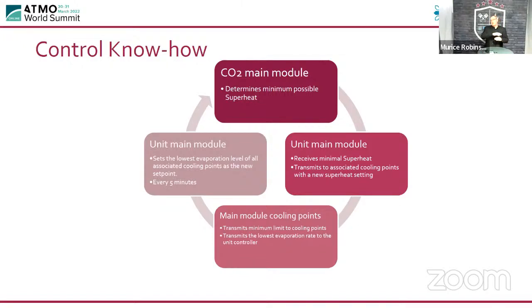At the same time, as we reduce the superheat, we are telling the rack controller to actually increase the suction temperature. So as the one comes down, the other one comes up, and we try to find the happy medium at that time with the correct ambient conditions and the correct performance of the system, how the store is trading, what the store temperatures are. All of those influencing factors are considered, and we get that as close as possible so we can get the maximum energy saving.